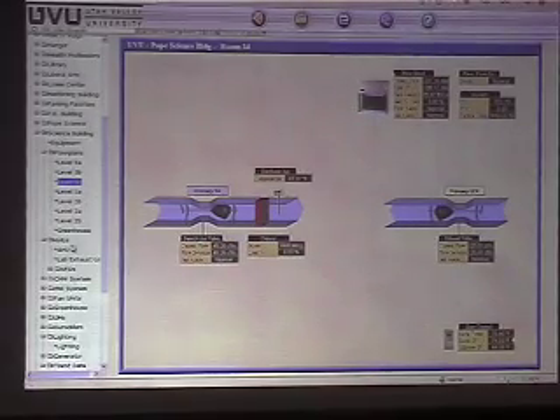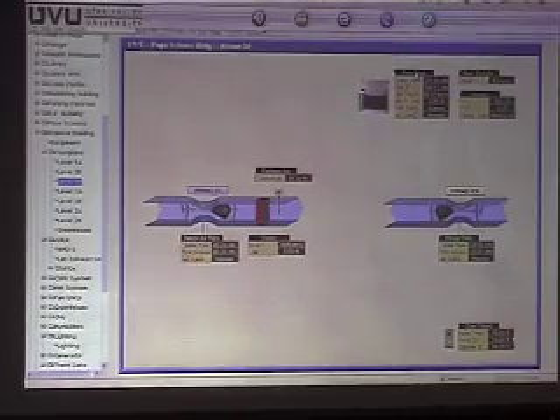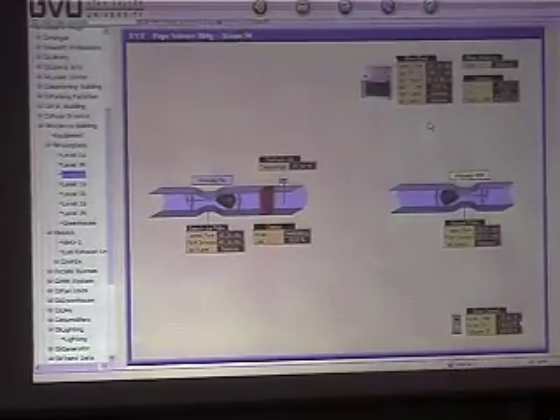So this is fairly typical. There are some variations. Some rooms have two of these supply valves, some have two exhaust valves. Some will show a snorkel instead of a flow hood, which pretty much functions the same way, other than that you don't have a sash position.